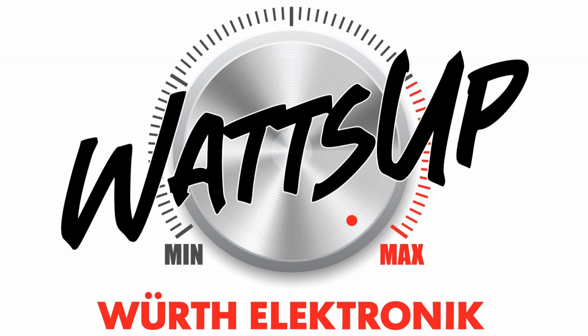Of course, if we have two Y capacitors, they will also act like one smaller X capacitor, but the opposite is not true. We can never use X capacitors in the Y position because of the open failure criteria.